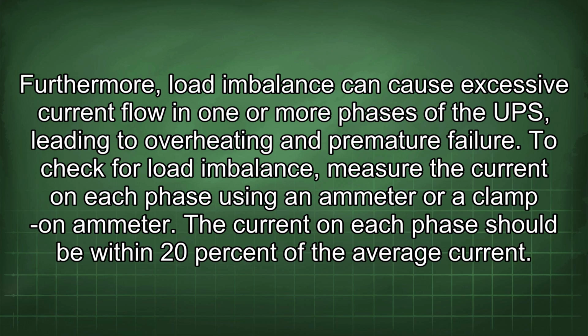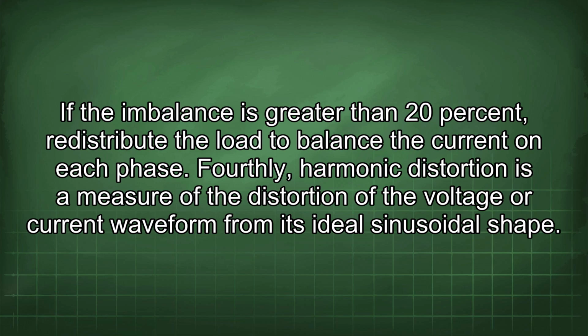To check for load imbalance, measure the current on each phase using an ammeter or a clamp-on ammeter. The current on each phase should be within 20% of the average current. If the imbalance is greater than 20%, redistribute the load to balance the current on each phase.